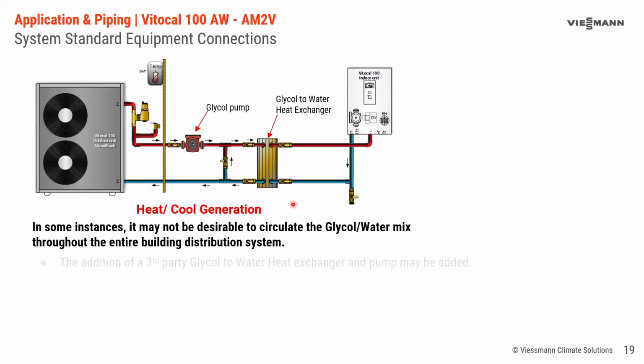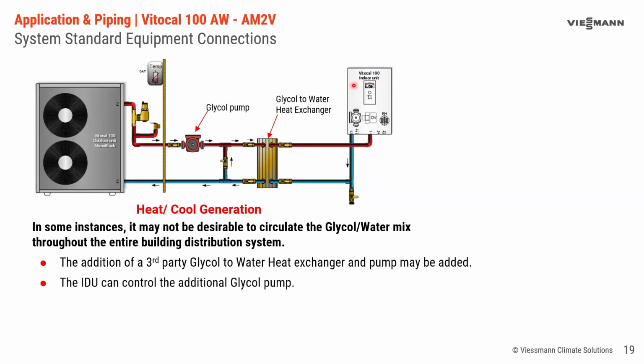So we talk about adding this heat exchanger, which means that we also have to add a pump, because now we basically have a separated flow system. So this pump here, being a glycol, we'll call it a glycol pump, sized correctly to move glycol from the outdoor unit to the heat exchanger. We're going to be controlling that from the indoor unit. On the indoor unit is an output called glycol pump, and we wire it to here. And then anytime the indoor unit has a call for energy, either to or from the heat pump, its pump is going to run, and we're going to circulate water this way.